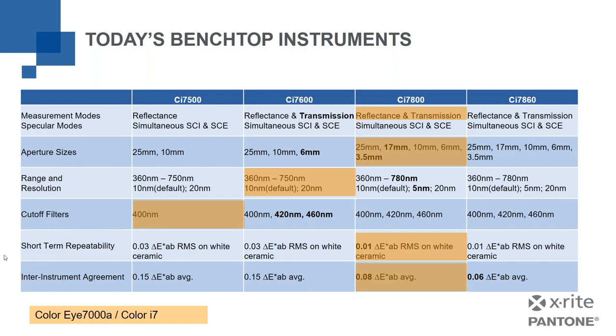All right, let's take one more look here. So someone says, Ci7 values were not matching Ci7000A. Okay? So the Ci7, an older instrument, and the 7000A had a lower level of agreement with one another, admittedly, than what we have with the 7800. The Ci7800, in almost all situations, there are a few exceptions, no doubt, but in almost all situations, the Ci7800 is a plug-in for a Color i7000A as far as the color is concerned. The inter-instrument agreement between a Color i7000A and a Ci7800 is the same as the inter-instrument agreement between two 7800s or two 7000As. They are drop-in replacements for each other.